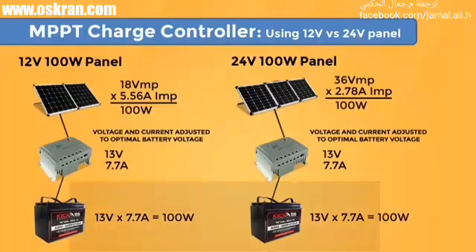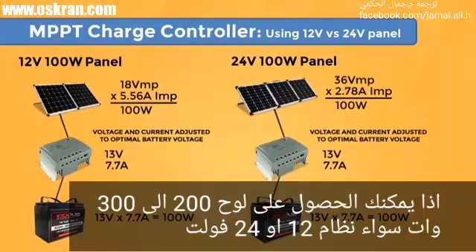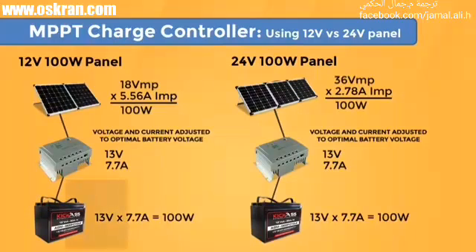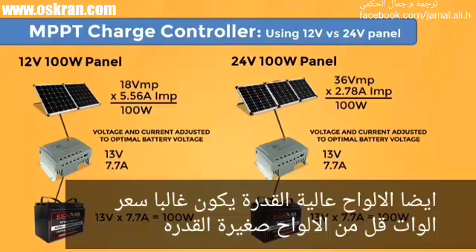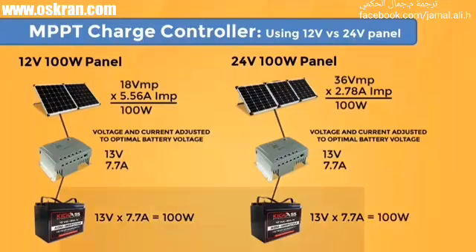This is very useful, as higher voltage panels are usually also higher wattage. You can get panels of 200 to 300 watts in a 20 or 24-volt nominal configuration, whereas 12-volt panels tend to go well under 200 watts. The higher wattage panels are also generally less expensive per watt. So depending on your system, using bigger panels with an MPPT charge controller can often be the less expensive solution overall, even though the charge controller itself is more expensive.